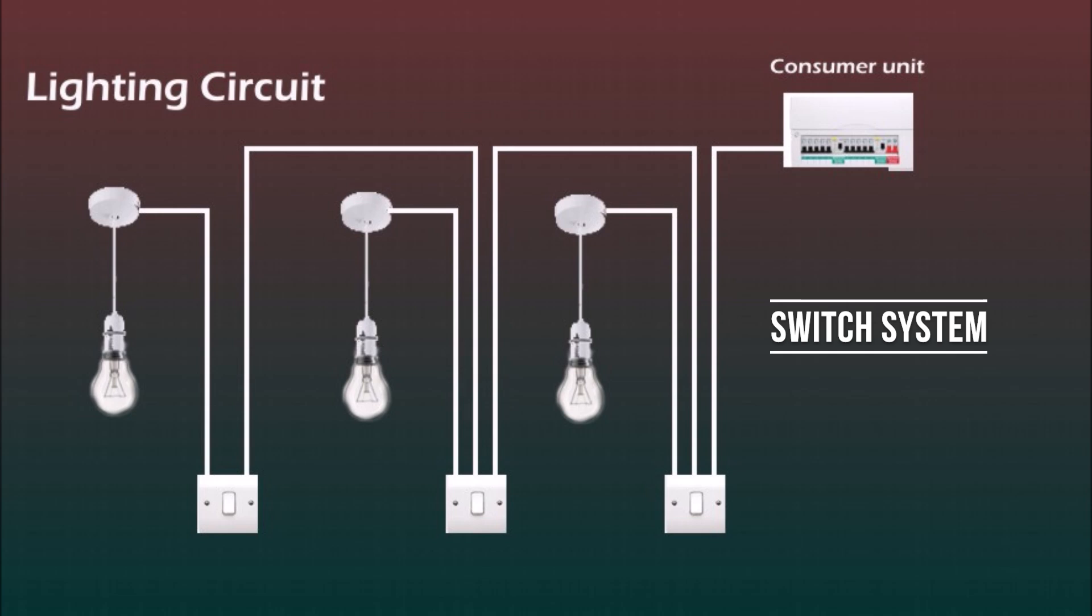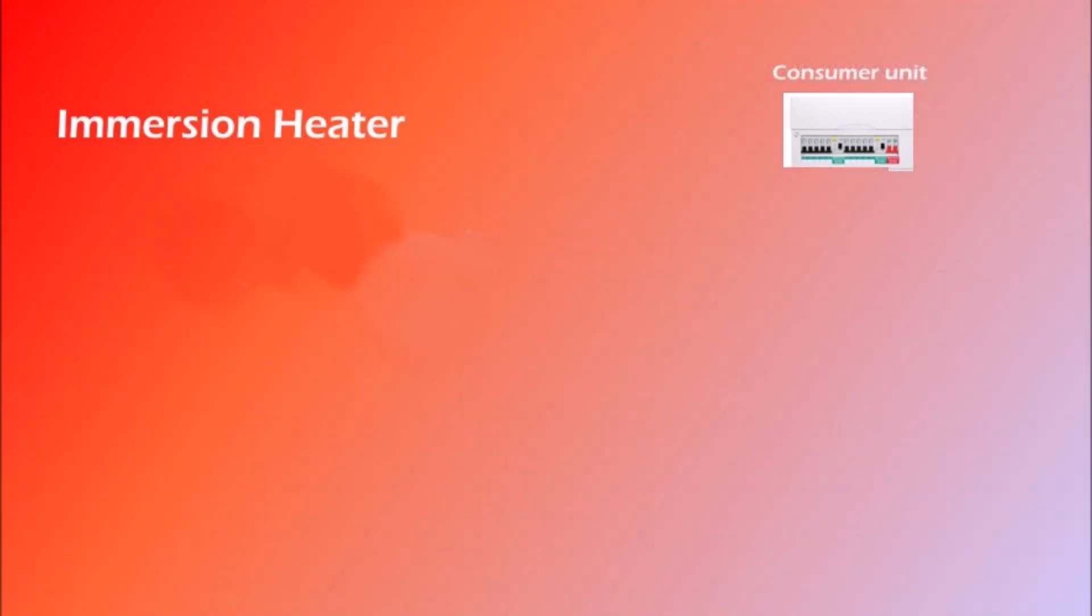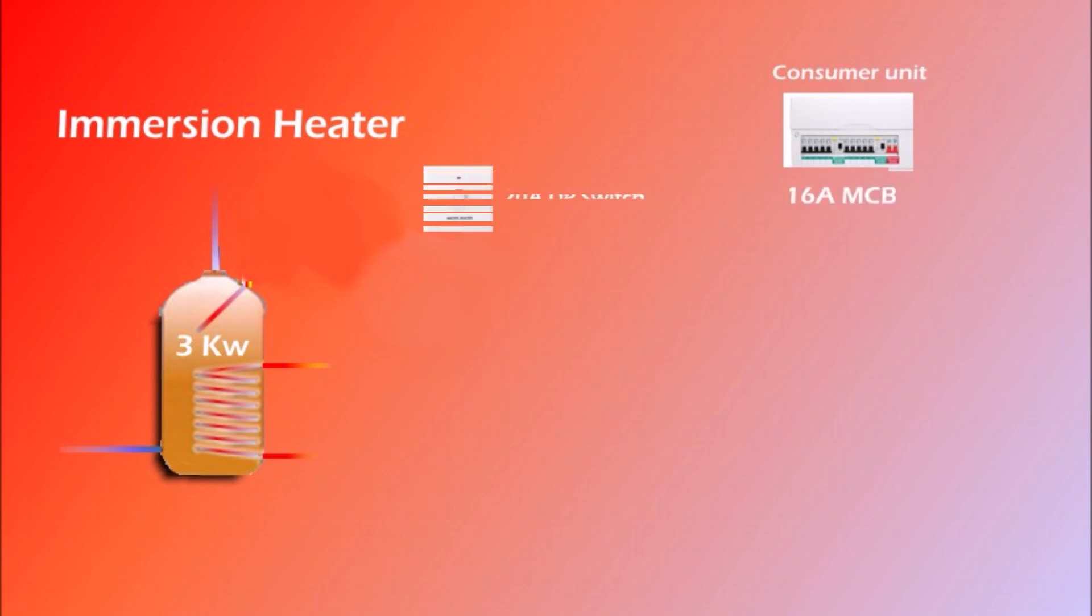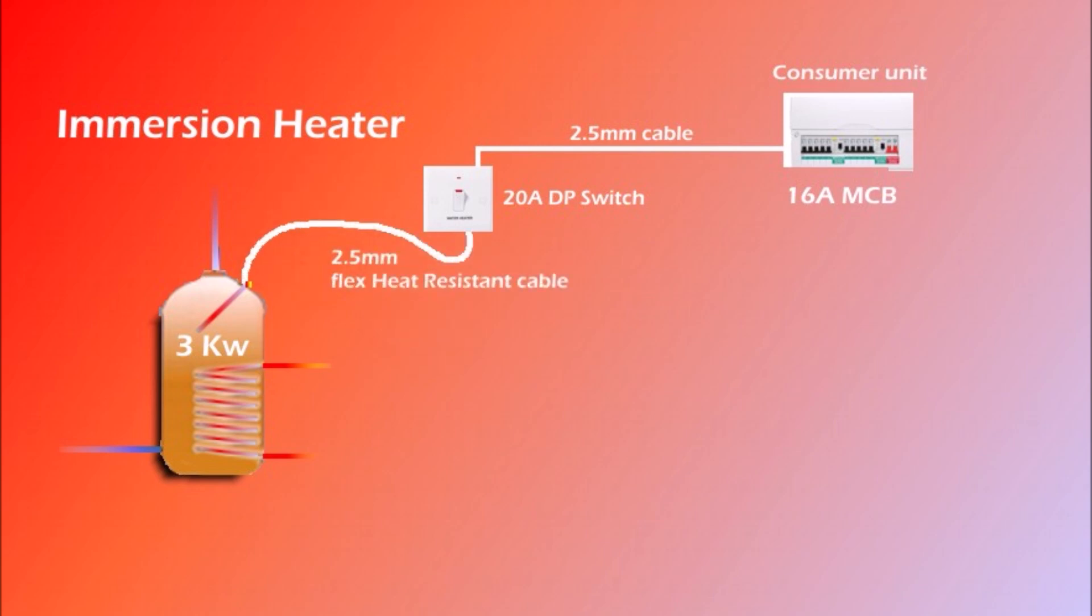And the last circuit that I'd like to show is the dedicated circuit for the immersion heater. So we've got the consumer unit on the right, the hot water cylinder on the left with immersion heater in it and a thermostat on top. And also between consumer unit and immersion heater we need to install 20 amp double pole switch. So the MCB for this circuit should be 16 amp and the cable size from the consumer unit to the switch 2.5mm twin and earth. Also the cable from switch to the immersion heater 2.5mm but flexible and heat resistant.